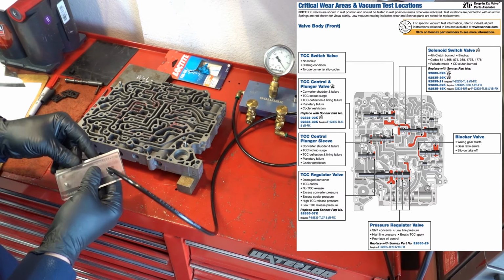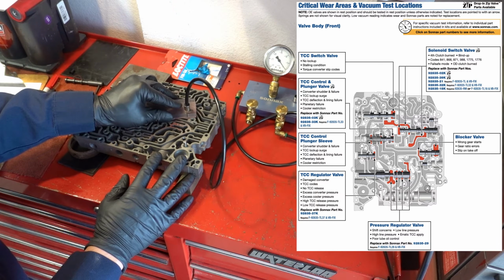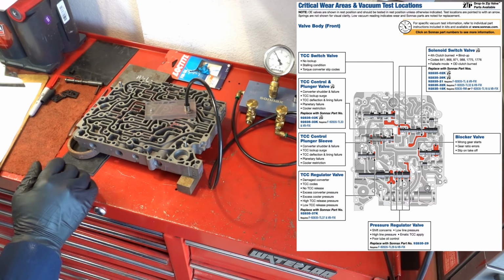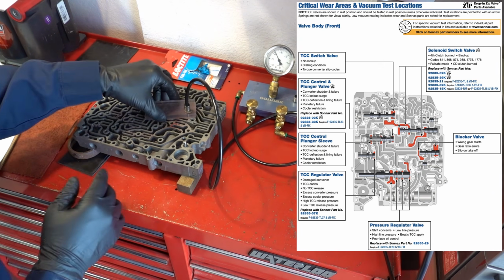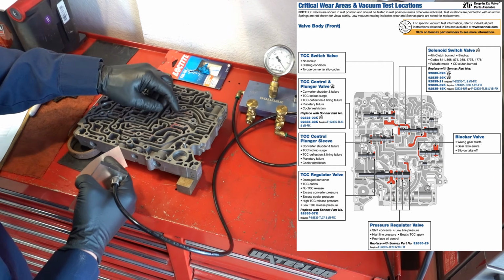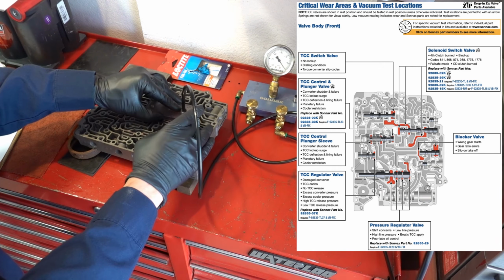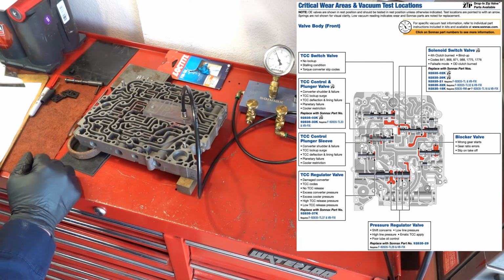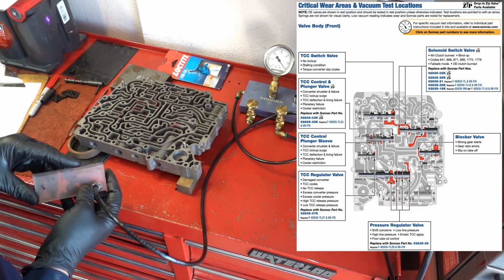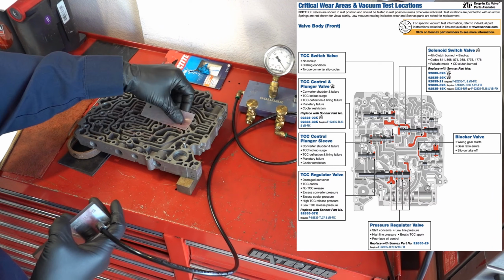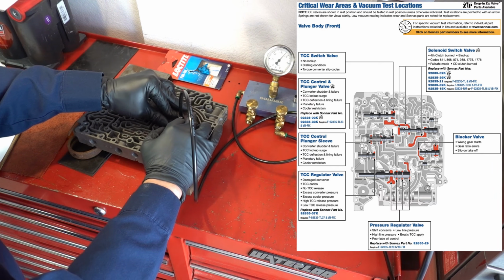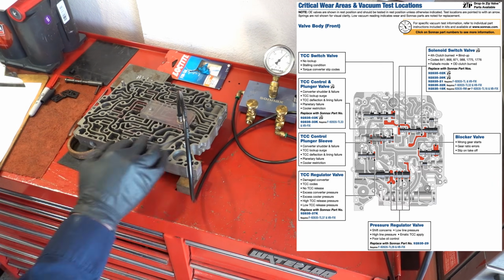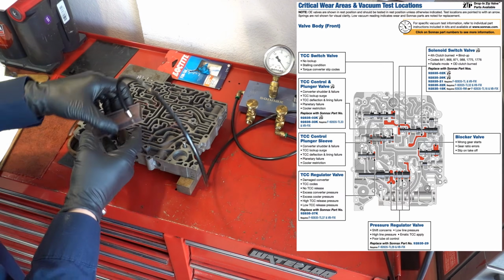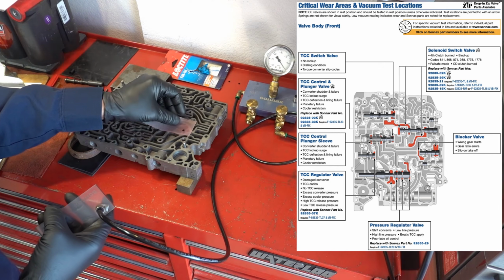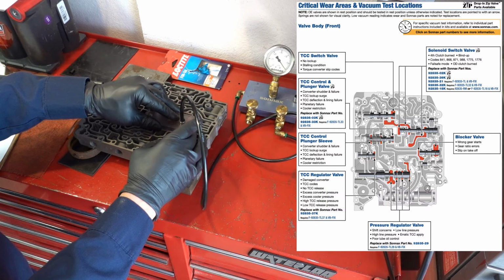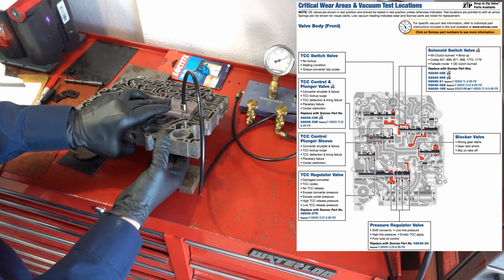Alright, now we'll move to the PR valve. It's going to be inboard. 19.5. Okay, third position in is going to be right there. There are 4 total test points. 19. Second position is this rectangular location. Okay, that looks like it's giving us just shy of 12. I'm going to record 11.5. It's obviously not an ideal result. And then now you've got this roughly Y-shaped position, or it looks kind of like New York State if it went on a massive diet. Alright, let's see if I can improve that reading.